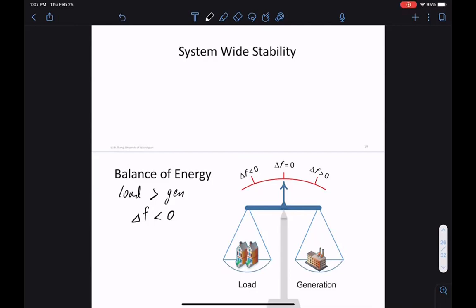So frequency goes down. The reason the frequency goes down is if you need to provide more power to the load than you're actually generating, you borrow power from the rotating masses in the system. They're rotating, they have some frequency. You borrow this power, so the frequency goes down because you're extracting power out of your short-term storage, which is in the form of rotating masses. So they rotate slower, and frequency goes down.